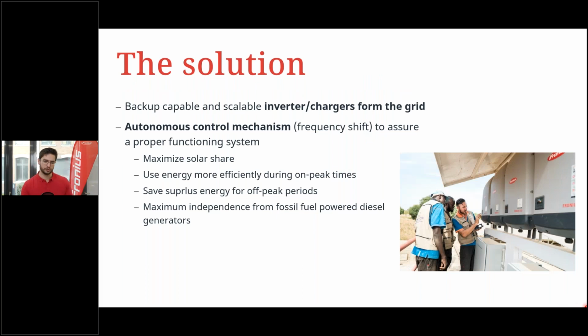Yeah, and the solution itself looks like this. We have the backup capable and scalable with inverter chargers, which do form the grid basically. Because if you think about the Fronius inverters, they do always need some kind of frequency and voltage to synchronize to. We're not able to build up the grid 24 hours a day, 7 days a week. For that, we have Victron, and then Fronius just synchronizes onto it. And this gives us an autonomous control mechanism with a so-called frequency shift to ensure a proper functioning system.